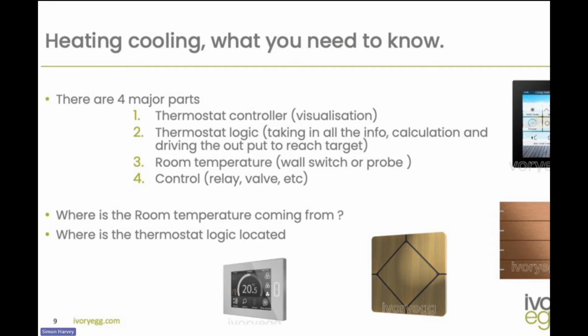Then we've got the thermostat logic. The thermostat logic and the thermostat controller sometimes can exist in the same product, but not always. You can have the controls for the thermostat and the logic for the thermostat in two different places, and we're going to show you what that looks like inside an ETS demo next. What the thermostat logic does is take into consideration maybe a room temperature. It could be a temperature coming from a switch, such as the Faraday switch or the Gira switch you've seen there, or it could come from a probe, for example a probe coming out of a floor or anything into the back of a switch. Basically, it looks at the probe temperature, it looks at what the customer's asked for, and then it makes a calculation and drives an output to reach that target, okay? And as one of the strategies is employed, as it gets closer to that target or busts over that target, it turns that output down or modulates the signal to keep it within there.